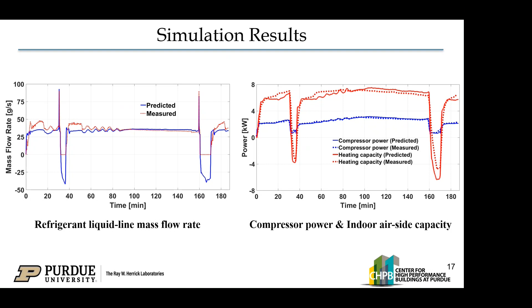We can see that during defrost cycle, of course, the heating capacity goes negative because you are taking heat from the indoor environment, and we can also validate the compressor power. These metrics are pretty good. Then, because we have a detailed frost model, we can predict the frost properties, the thickness and density, for selected control volumes. So CV1 means the first control volume, which is close to the inlet of the refrigerant, and CV30 is close to the compressor, the outlet.